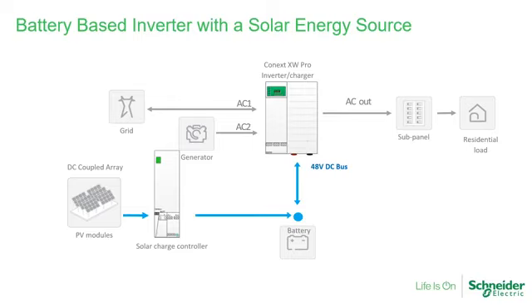is that now I can actually communicate between the devices and decide at what point I have excess power. Let me give you an example to clarify what I'm trying to say here. In most cases where a customer is requiring storage, what we are asked is that the storage is held for an emergency. There's a power outage, so the customer wants to make sure their batteries are fully charged in case of a power outage. So the priority is the solar array will charge the batteries first. However, in a grid-tied system where you haven't had a power outage, the batteries are going to be full from the day before because if you don't use the batteries, they don't just simply discharge overnight.